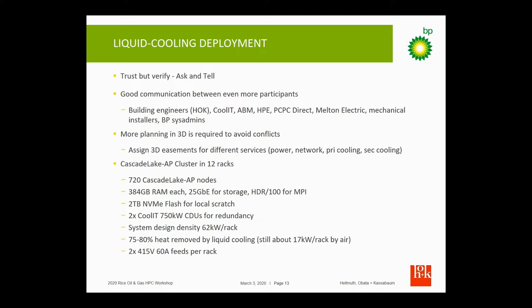We found that we essentially had to talk through a lot of these options and issues with all the different vendors involved. With water cooling, you've got to talk with even more vendors, including your building engineer. It's very important to understand the limitations of the building and what different options it can handle — for example, our building has an option in the cooling distribution to use either a three-way valve or a two-way valve, and that determines whether you're varying the volume of liquid or the temperature coming back. Some systems are designed to handle one versus the other.